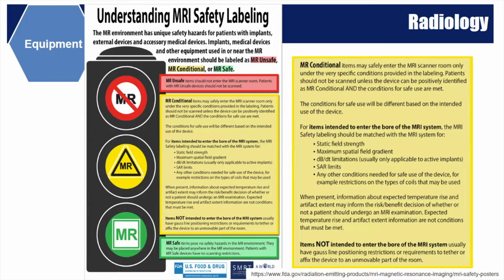MR conditional items may safely enter the MR scan room only under very specific conditions provided in the labeling. Patients should not be scanned unless the device can be positively identified as MR conditional and the conditions for safe use are met. The conditions for safe use will be different based on the intended use of the device. For items intended to enter the bore of the MR system, the MR safety labeling should be matched with the MR system for static field strength, maximum spatial field gradient, SAR limits, etc. Items not intended to enter the bore of the MR system usually have Gauss line positioning restrictions or requirements to tether or affix the device to an unmovable part of the room.